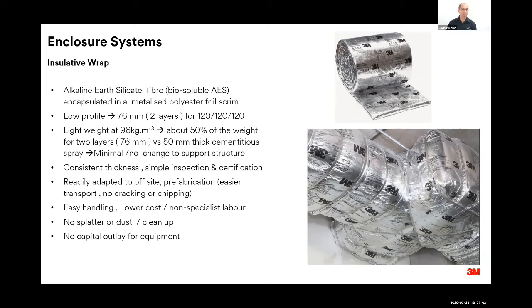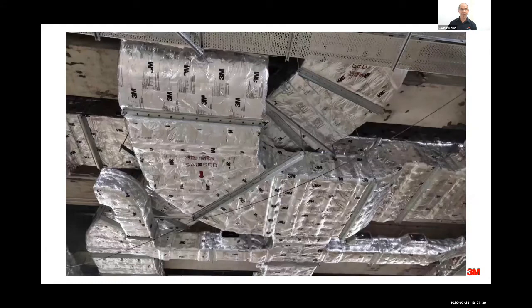It's readily adapted to off-site and prefabrication methods because it's a flexible system and there are no issues with cracking or chipping. It's easy to handle and you can use lower cost, non-specialist labour. Typically, an insulation lagger could do this sort of work, as well as specialist fire installers. There's no splatter and very little dust, very little to clean up, with no capital outlay for equipment. Here's a picture showing a complex arrangement of ducts, all fire protected or enclosed with 3M 615 Plus duct wrap.